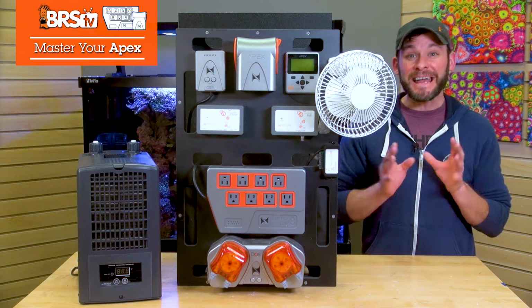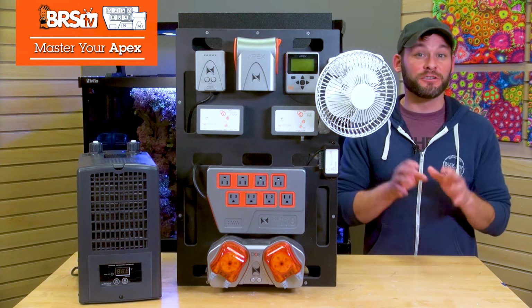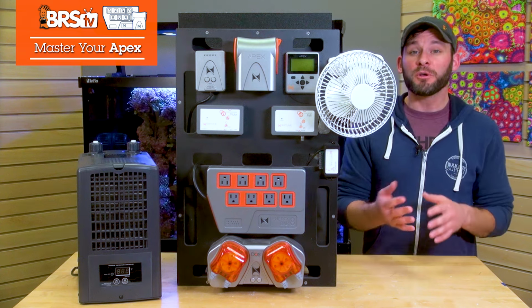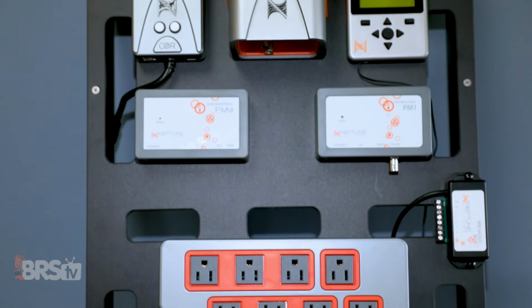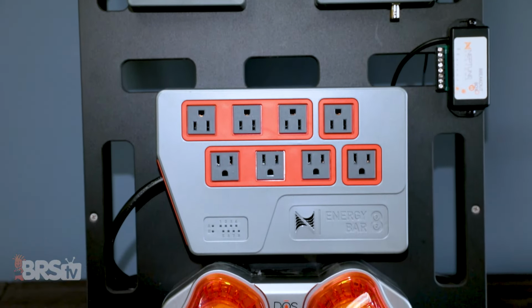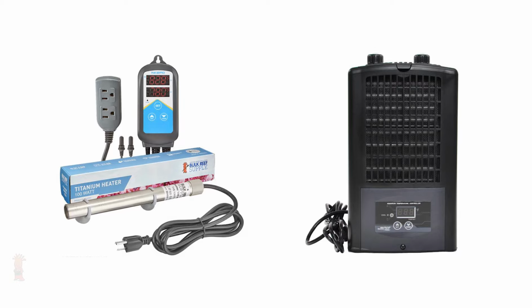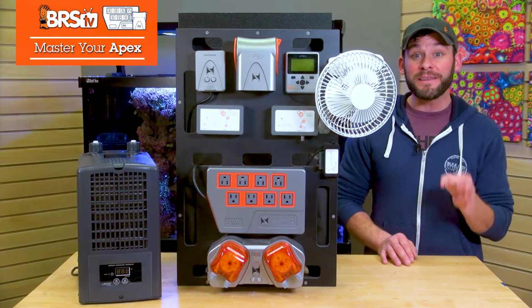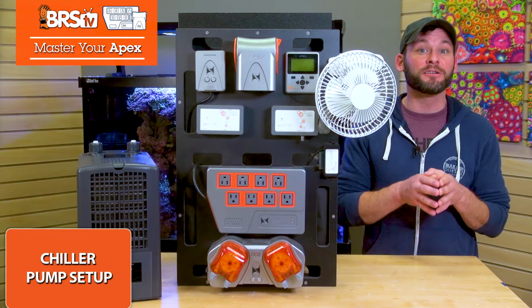I'm gonna go with the second option, not only because that's the way that the chiller task function sets it up for you, but also because having your Apex in control allows you to more accurately balance your heaters and chiller from fighting against each other. So with that, the first thing to do is set up your chiller feed pump.